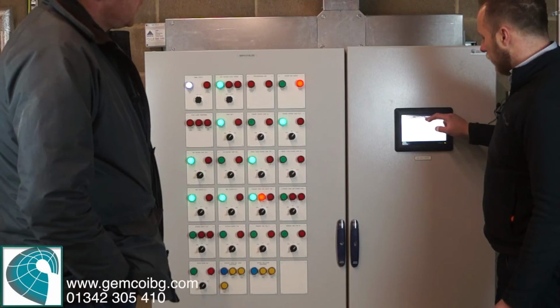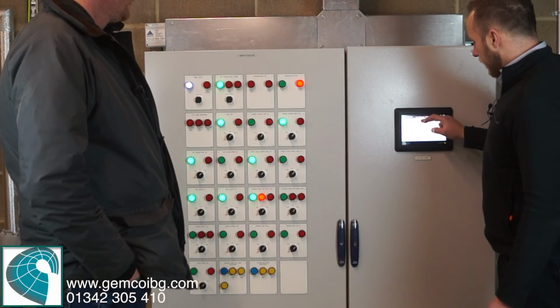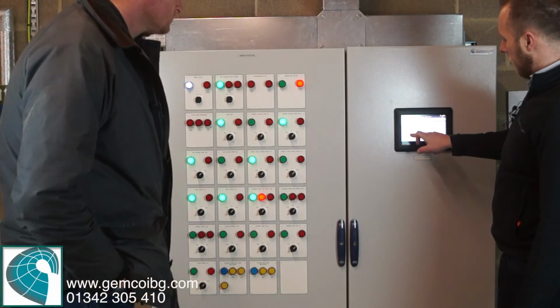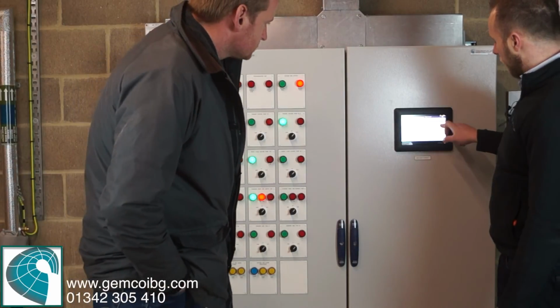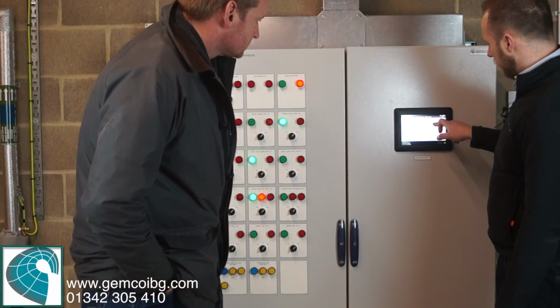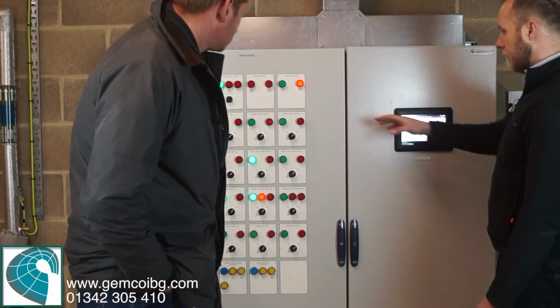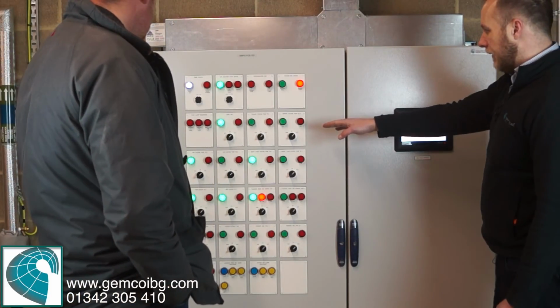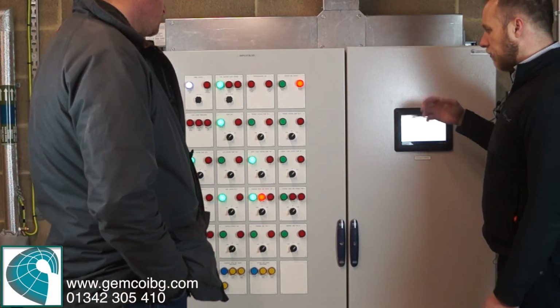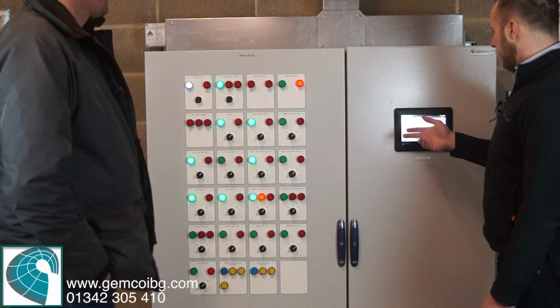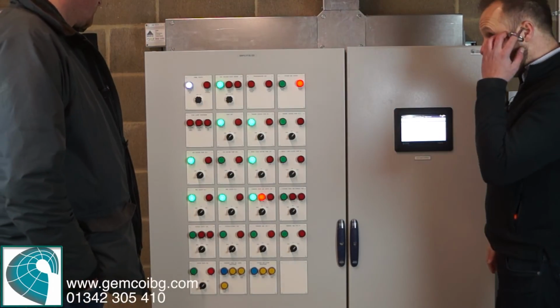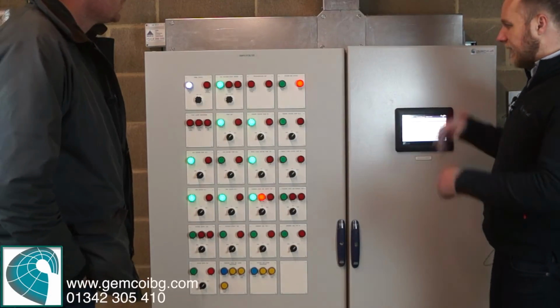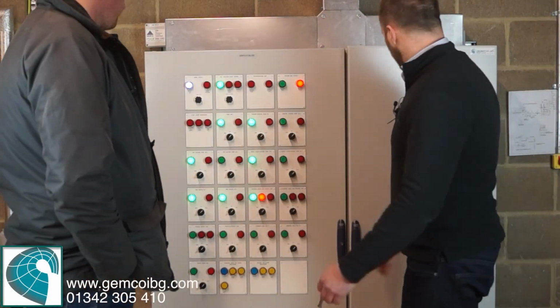So you'll have to actually go down, you find the switch that says whatever pump it is, primary pump fault reset, and you just turn it on. What it will do is it will go on for a sec, and then it will switch itself off, and it will reset the software, and it will come back on. So all it does is it resets the latch in the software that's holding it off.